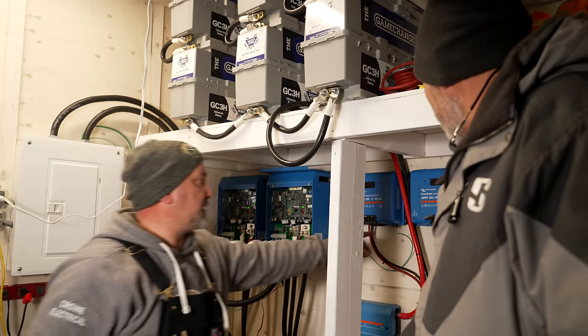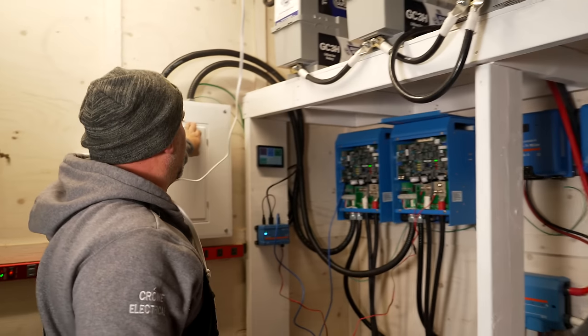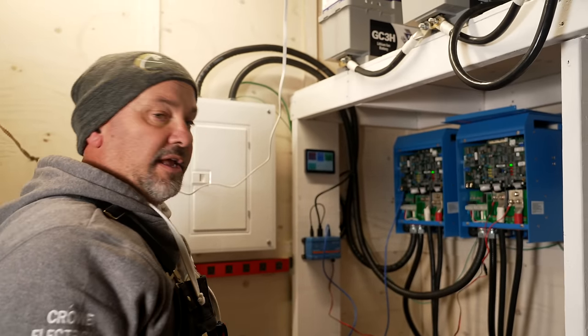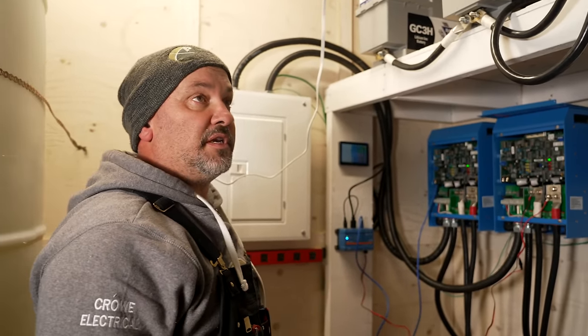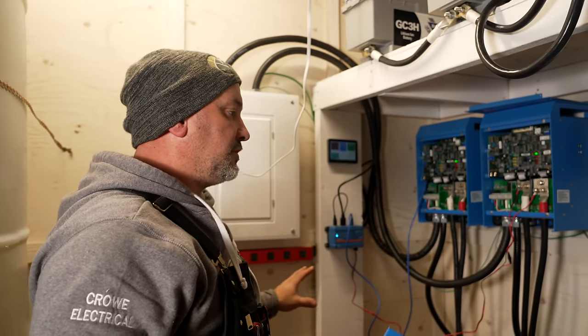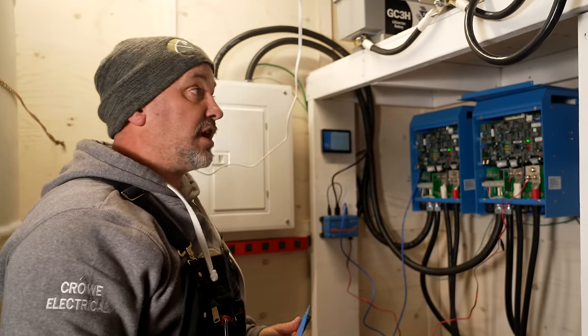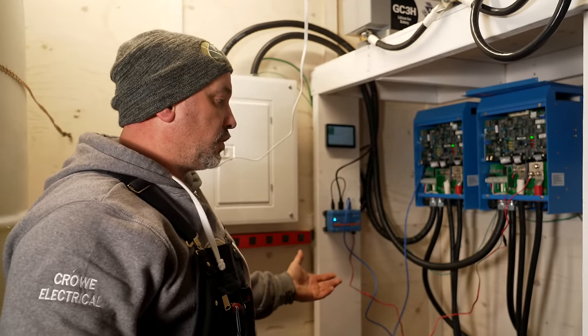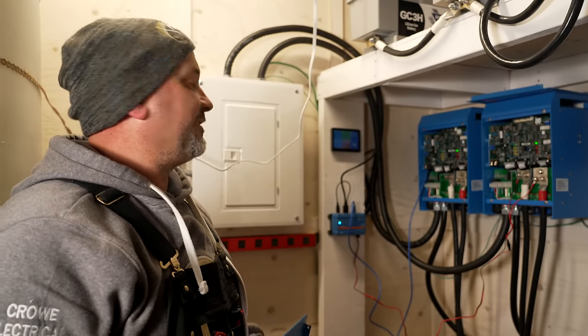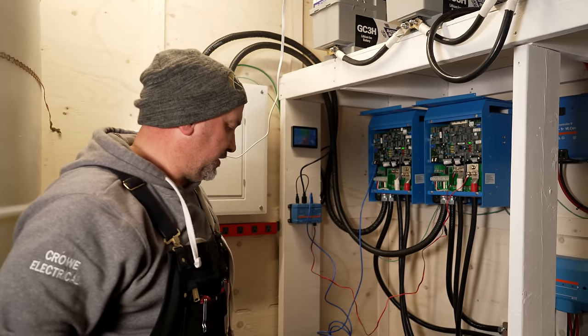Yeah. So basically, what I've done is each component is just bonded through and into the panel, and then from the panel it goes through a ground wire down. And then we dug a hole that's 2 feet deep, with a ground plate, so that basically keeps everything at the same potential, and everything stays safe in case something was to happen. Say, a lightning strike, something came apart, and there's a short for whatever reason. Right. Tornado happens or whatever. Hopefully not. So yeah, that's basically the system. That's what we've got hooked up so far.